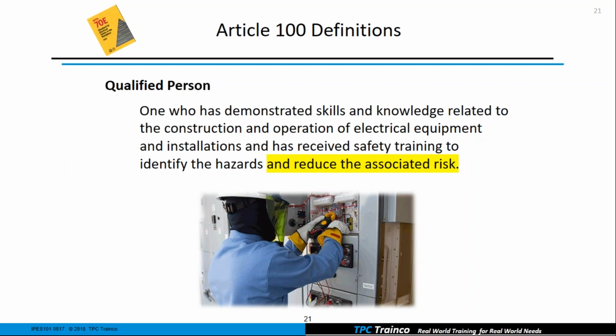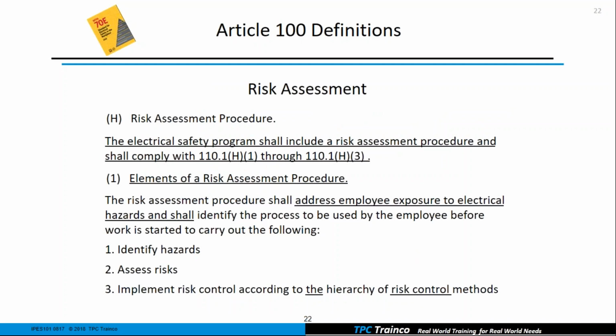But basically it always has been a person that can demonstrate that they do have skills and knowledge related to the equipment they're going to work on, and has received some safety training to identify the hazards. And now they put in "and reduce the associated risk." So risk assessments are extremely important in NFPA 70E. Before we approach a task, we've got to do some type of risk assessment to identify those hazards, to mitigate those hazards, and they give us a hierarchy for how we can do that, and I'm going to show you that coming up here. But risk assessments have now even been put in the definition of qualified person. So you can see they have played a little bit with risk assessment.